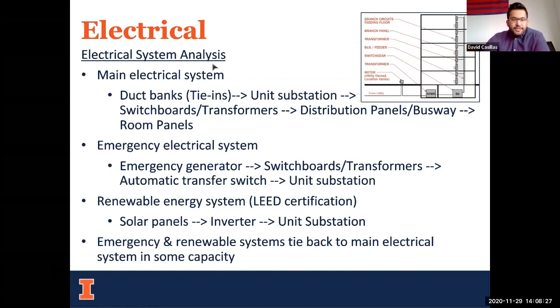There's a main electrical system, which consists of the tie-ins, or duct banks, connected to a unit substation in the basement. This is connected to the switchboards and transformers in the basement, and then to the distribution panels and busways located at each electrical room on each floor, which connect to the individual room panels.